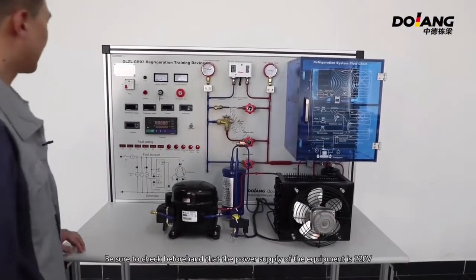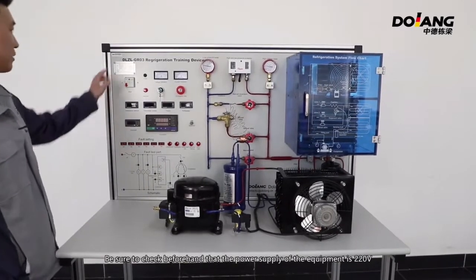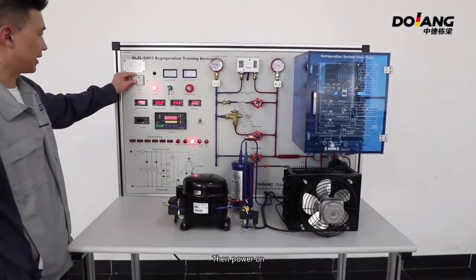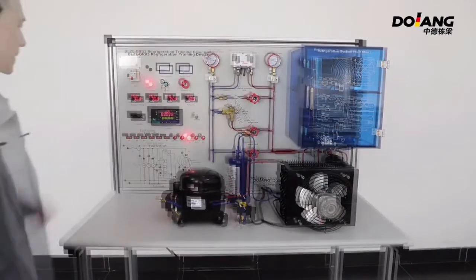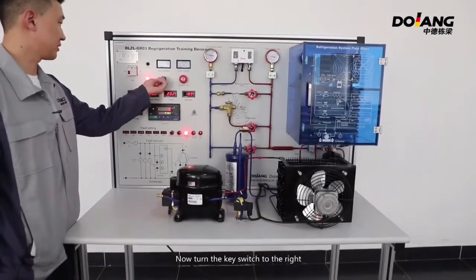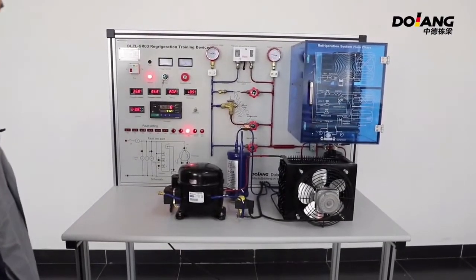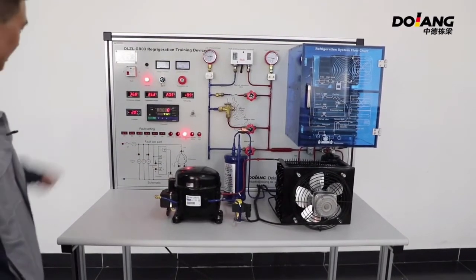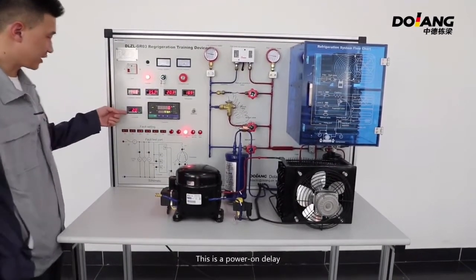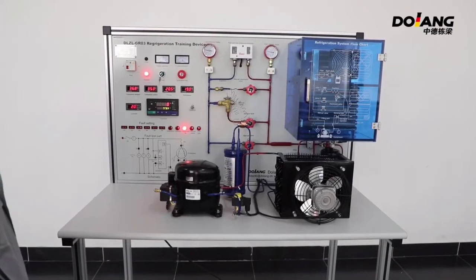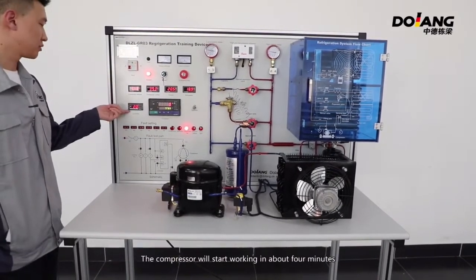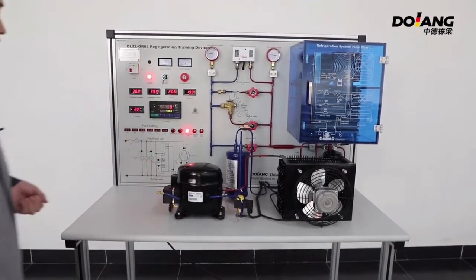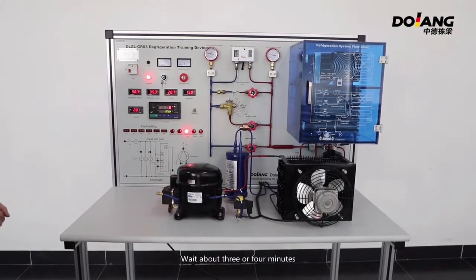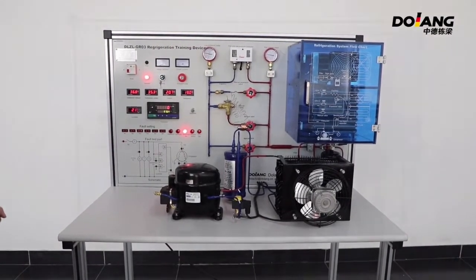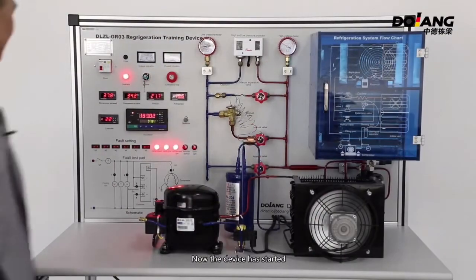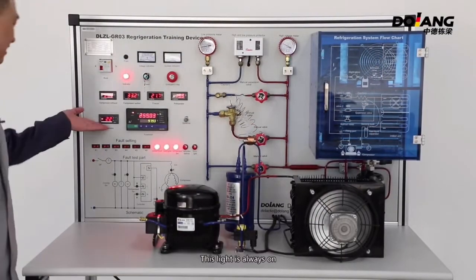Power on now. Be sure to check beforehand that the power supply of the equipment is 220 volts. Then power on. Now turn the key switch to the right, the light is flashing. This is power on delayed. The compressor will start working in about 4 minutes. Wait about 3 or 4 minutes. Now the device has started. This light is always on.